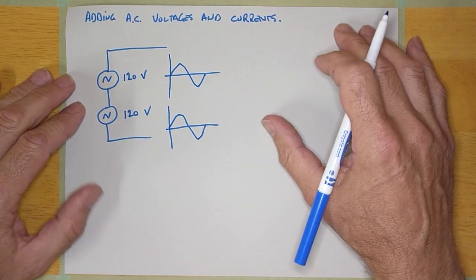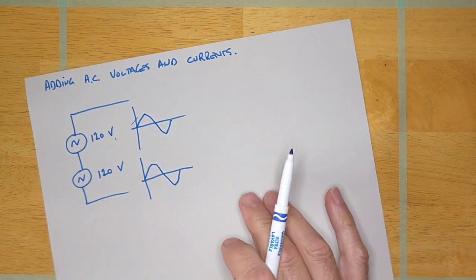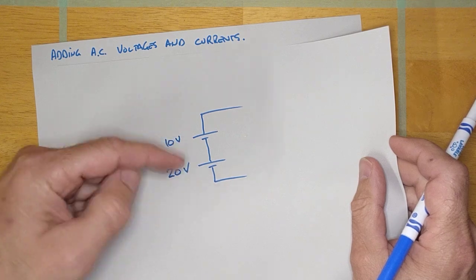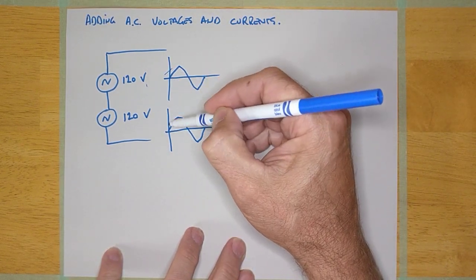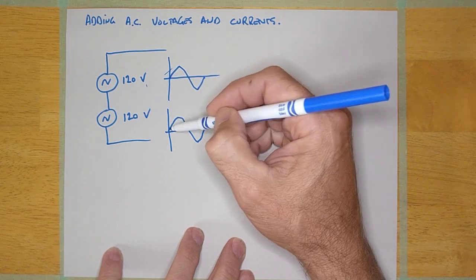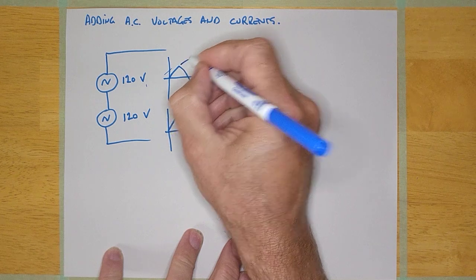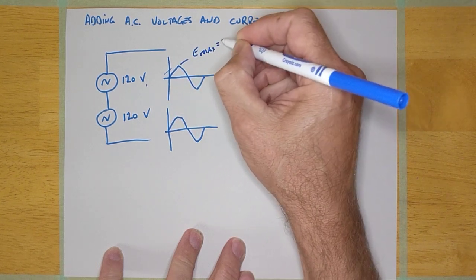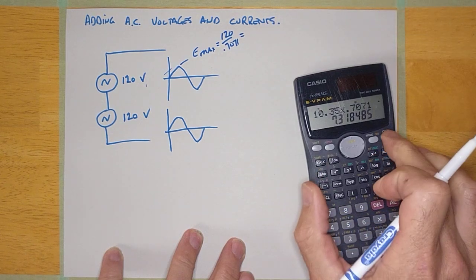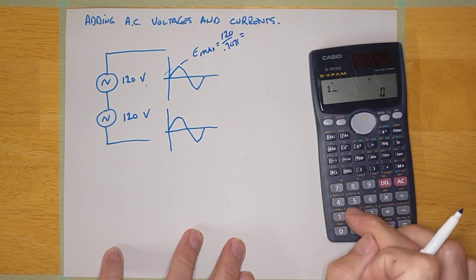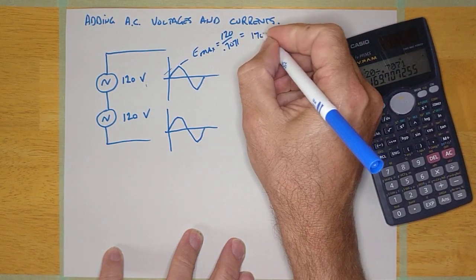The best way to figure out what's going on here is to think about our DC circuit, where I can just add the two voltages together and get the sum. But these voltages are always changing. So what's actually occurring is I've got to add the two instantaneous values of voltage together along the entire sine wave. Now, if this is 120 volts, that's the RMS or effective value. It means that the max value, which is equal to 120 over 0.7071 — E effective over 0.7071 — comes out to basically 170 volts. It's 169.7, so we'll call that 170 volts peak.